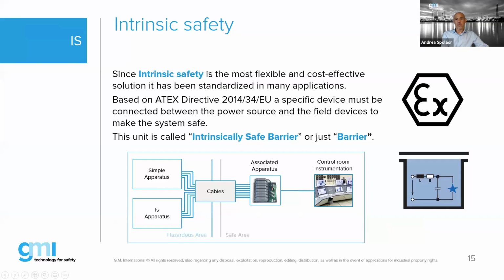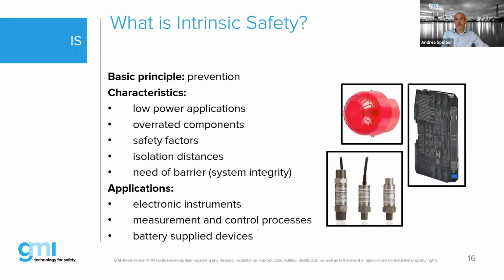Okay, so let's go to intrinsic safety. We would say that intrinsic safety is the most flexible and cost-effective solution. It's used because it's really simple and low-cost. The device mentioned in the first slide that must be used in the application is called an intrinsically safe barrier, or just barrier, which is the most known name in the market.